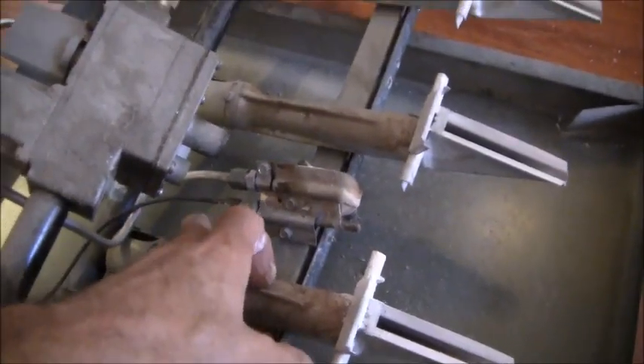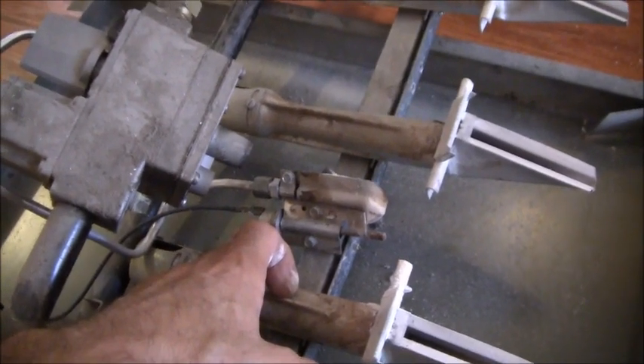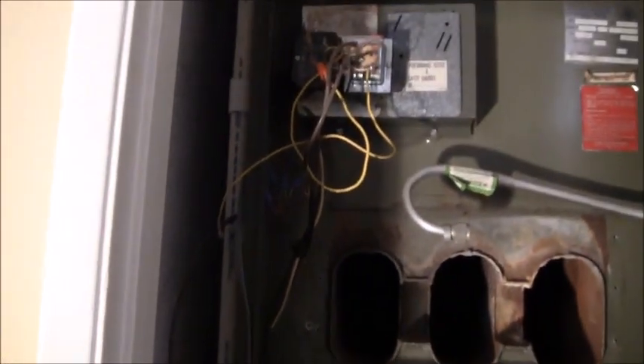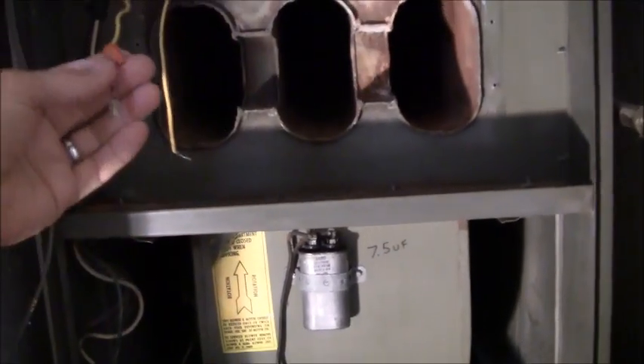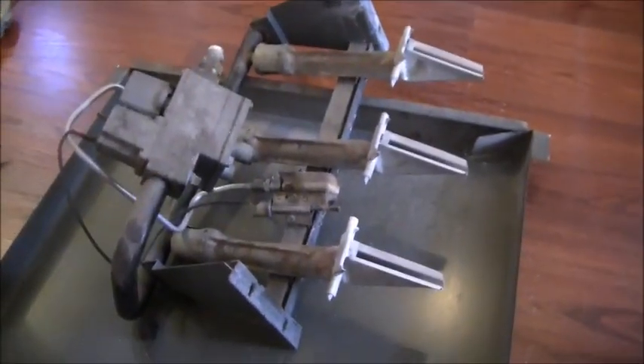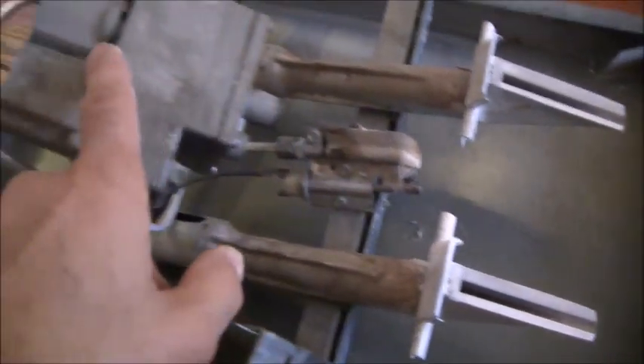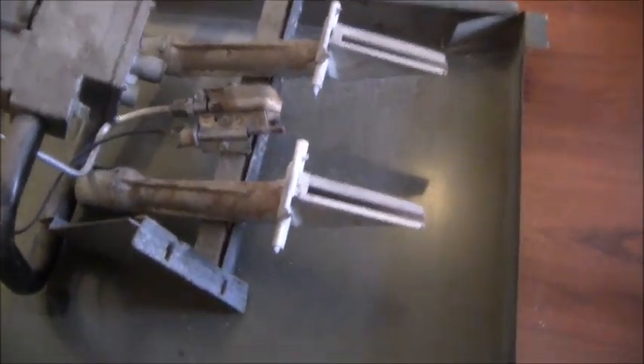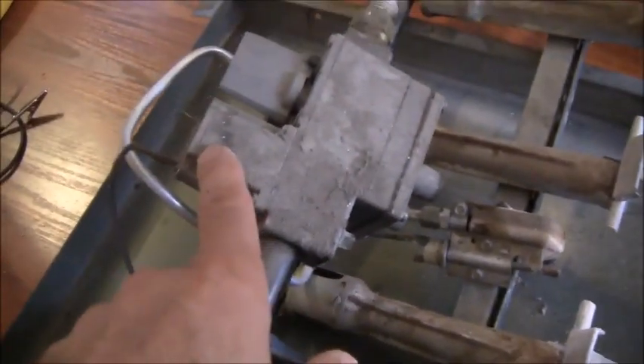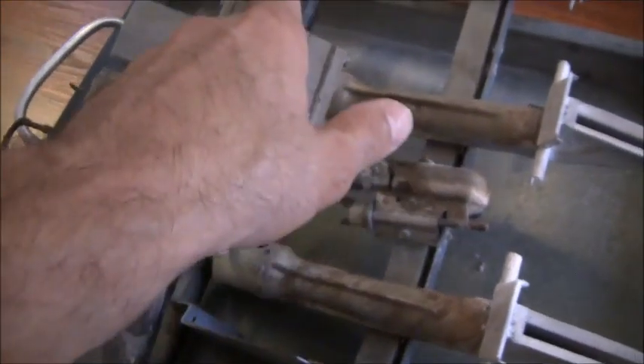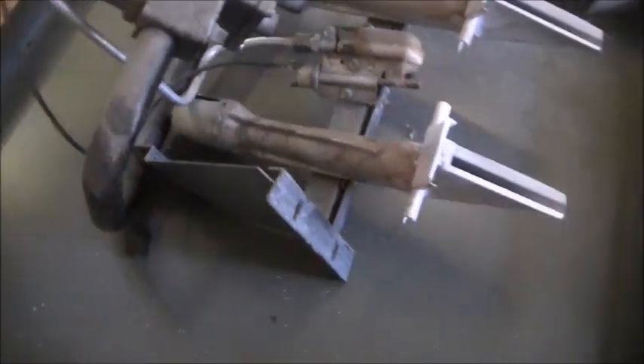Then you can see one lead of the thermocouple goes to the gas valve. So what happens is it comes the one wire, the yellow wire. There's two yellow wires that I disconnected, if you remember. That was this wire and this wire here. So this wire goes to the thermocouple. This yellow wire here goes to the gas valve. So that's how you complete the circuit. So the thermocouple is telling the gas valve, hey, I've got a flame, it's okay for you to open. This is how the system operates. This produces a little mini voltage that operates a coil in here that allows this valve to open to allow the gas to go through into the burner manifold.